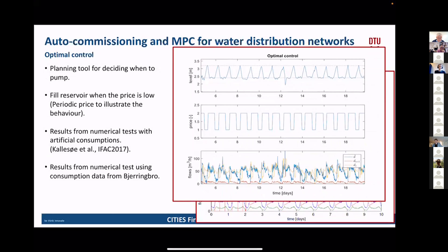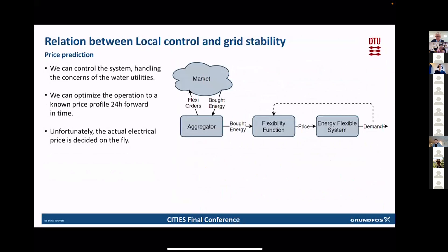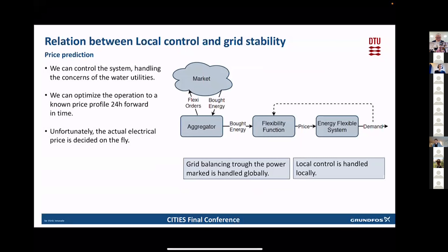The MPC controller operation is shown here, where the top plot is the level in the water tower, an artificial price signal with a staircase form so you can understand what's happening, and then the flows at the bottom — blue is consumption of the lower zone, green the upper zone, and red is the pump flow from the pumping station. What we can see is that we have high flow at low prices, exactly as with John's presentation. The water tower is filled when the price is low, and we are discharging the water tower when the price is high. We see exactly the same with the yellow signal, which is the pump consumption, because our prediction is not that good.